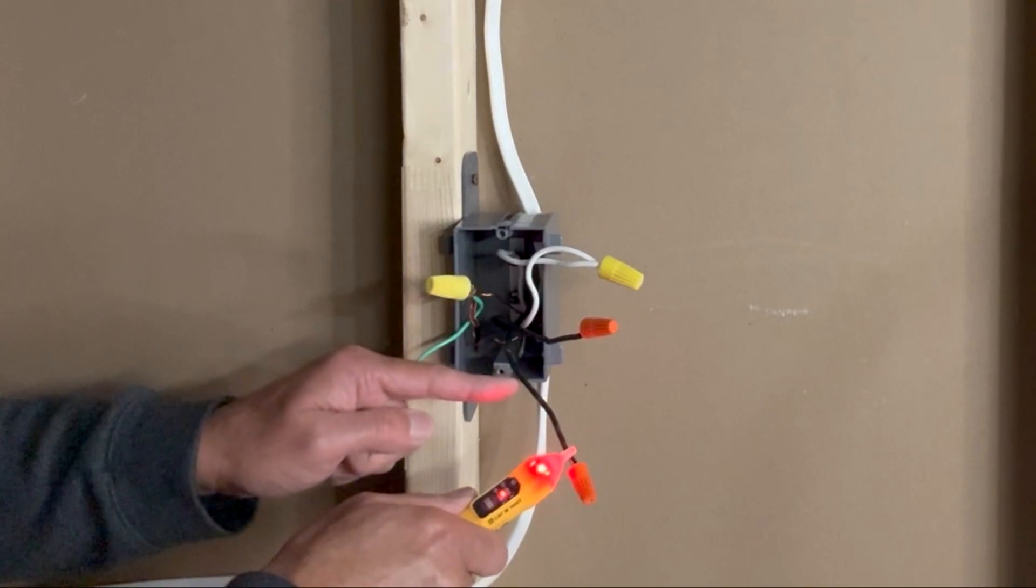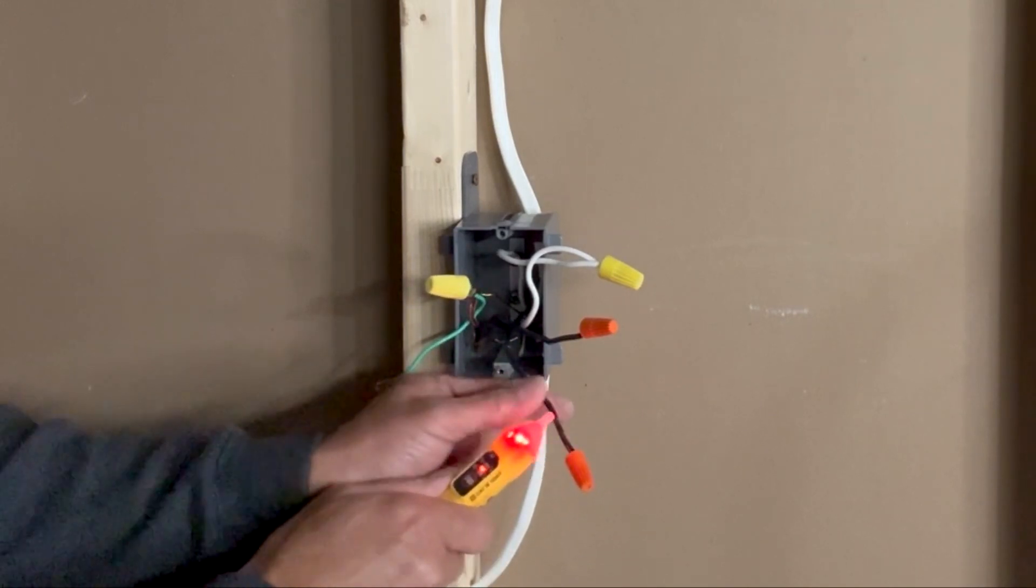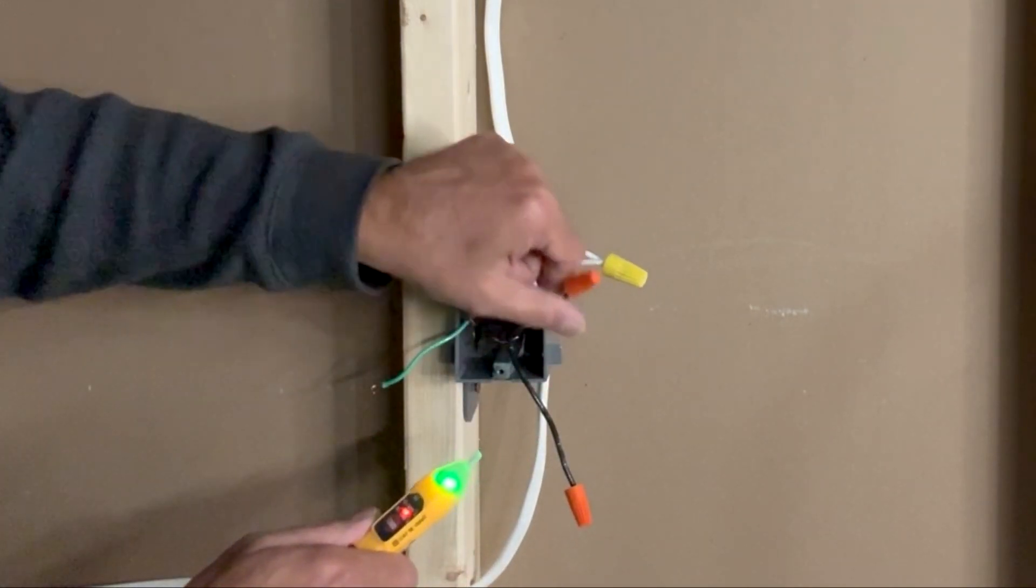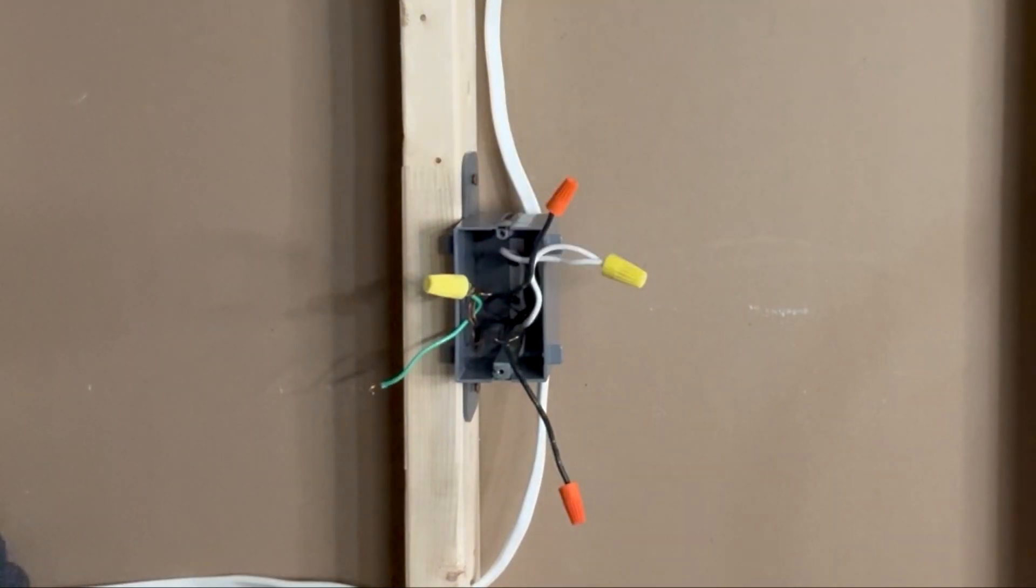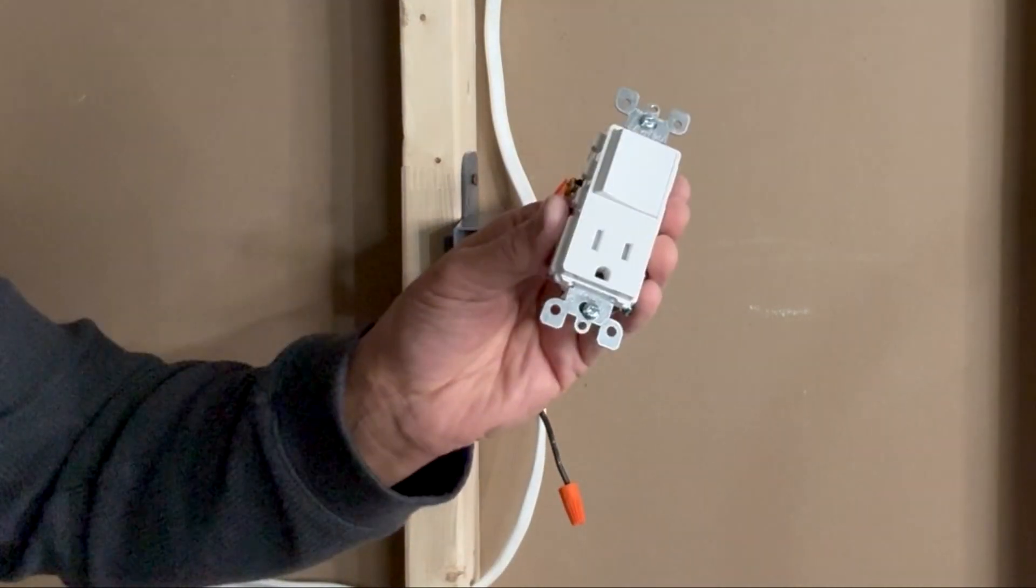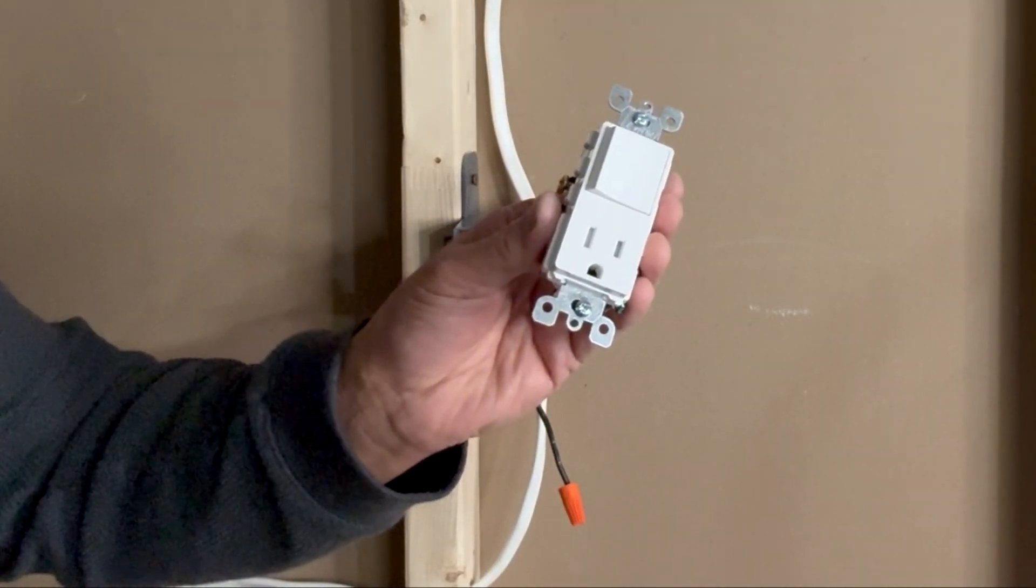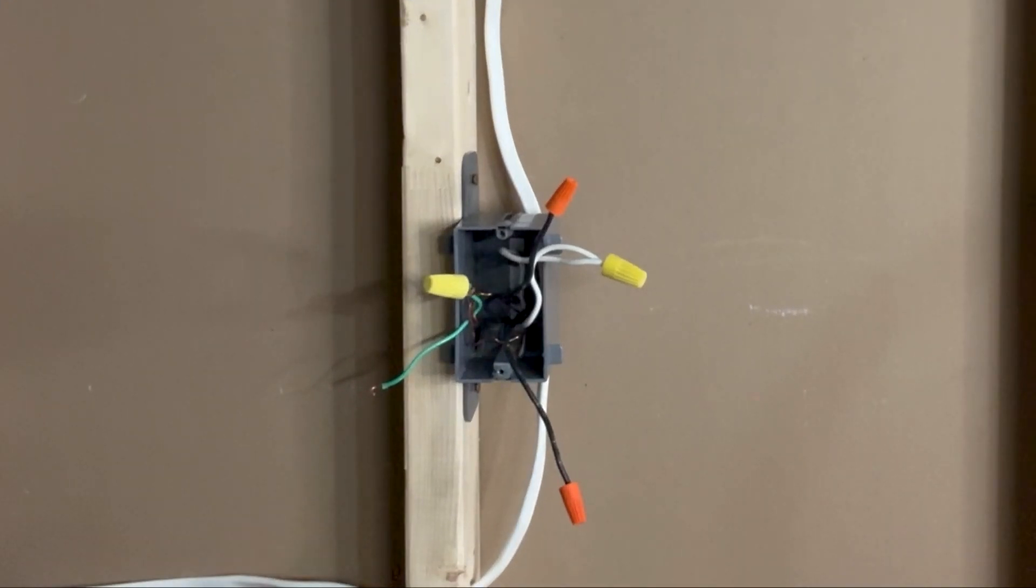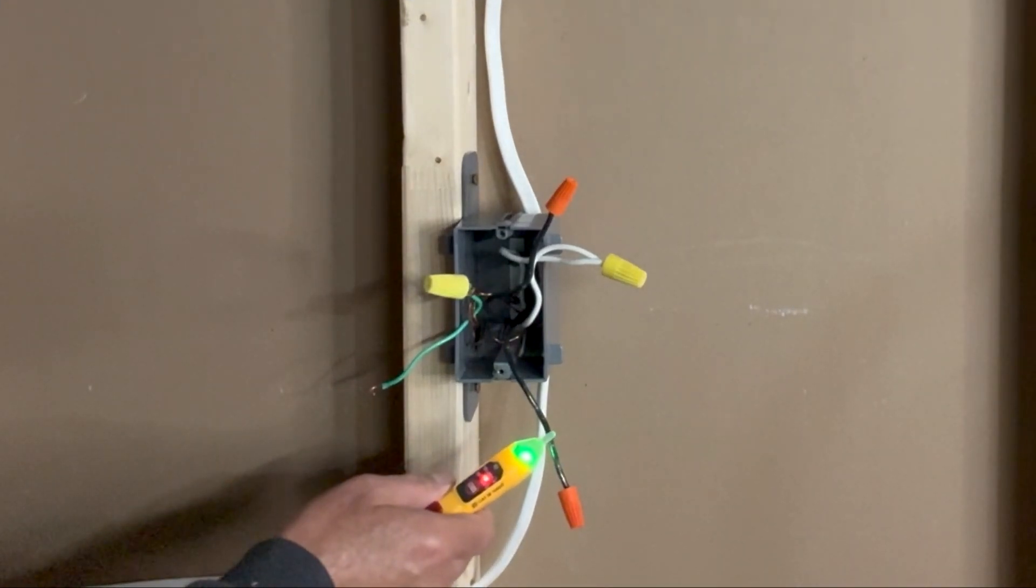So this black wire at the bottom is my line wire. I will keep it down and keep this wire up. I will turn off power again and then connect the new switch and outlet combination device. Power is off but I will double check to make sure that it is really off.